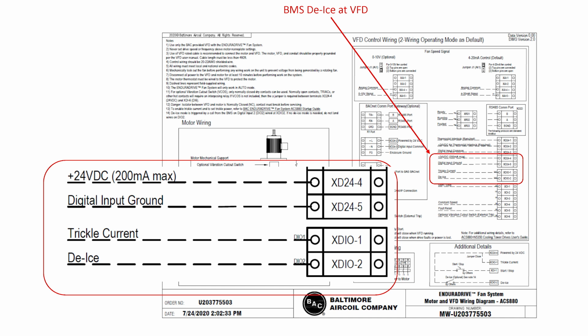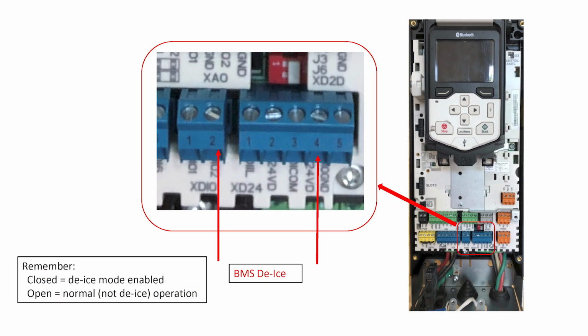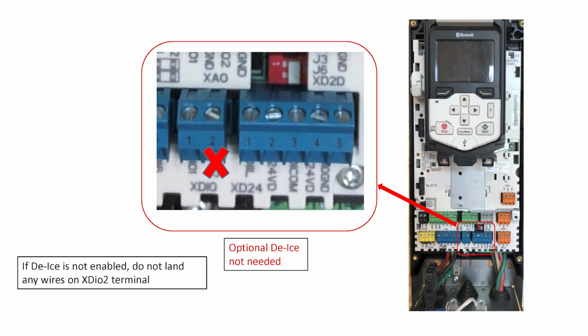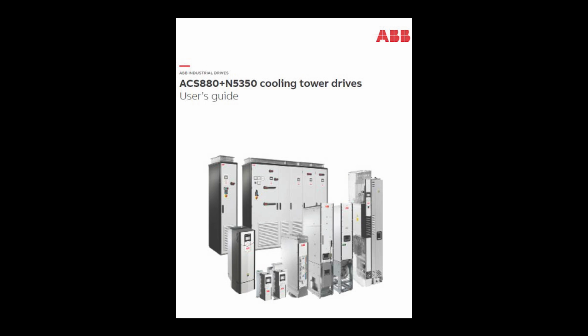XD24-4 is labeled as 24 volts, and XDIO-2 is labeled as DIO2. Remember, closed equals de-iced. In this mode, the motor runs backwards. Open equals no de-icing. If the BMS de-ice command is not required, do not land any wire on XDIO-2. If you want more detail on correct wiring, see the ACS880 plus N5350 Cooling Tower Drives User's Guide.